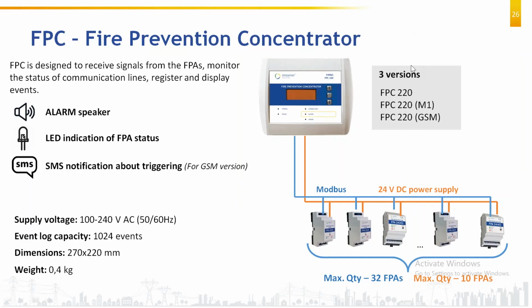What is the auxiliary supply requirement of FPA? The FPA auxiliary supply required is 24 volt DC. One FPC can power up to 10 FPAs. The thing is that FPC takes input from around 32 FPAs, but it can power only 10. So for the rest of the FPAs, you will need an external power supply.